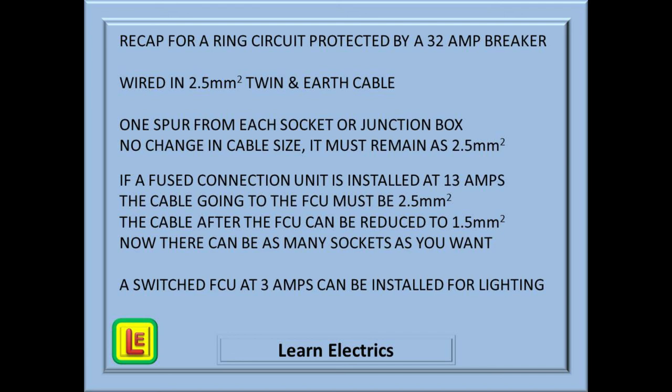If a 13 amp fused connection unit is installed then the cable going from the main ring to the FCU must still be 2.5mm. The cable after the FCU can now be reduced to 1.5mm. Because of the 13 amp FCU there is no limit to the number of sockets after the FCU.